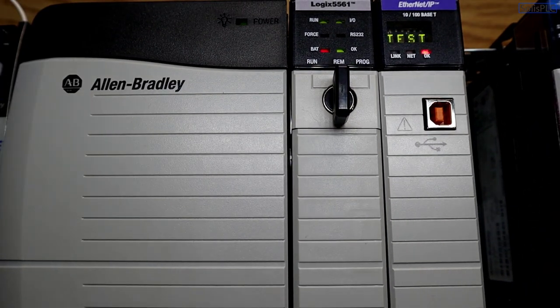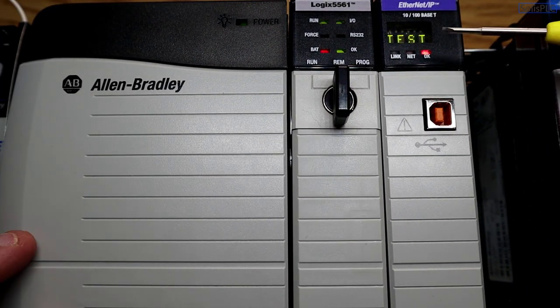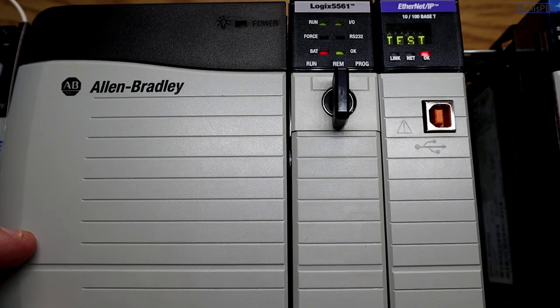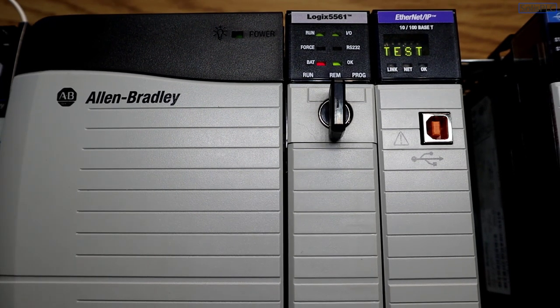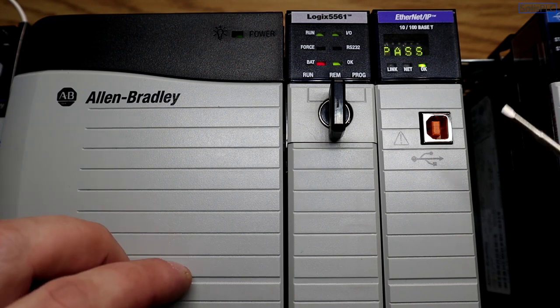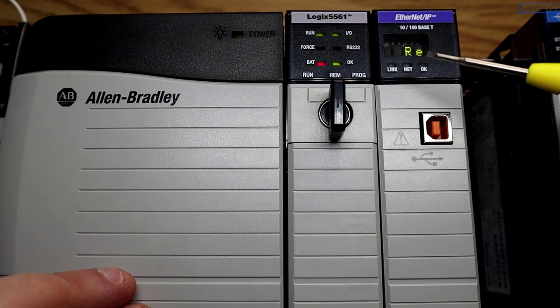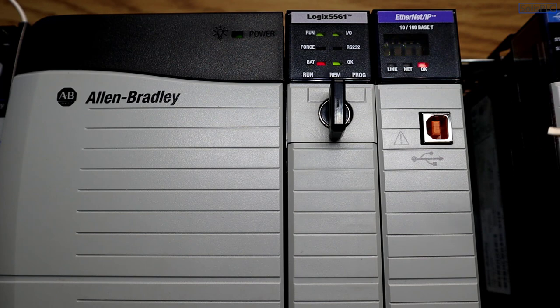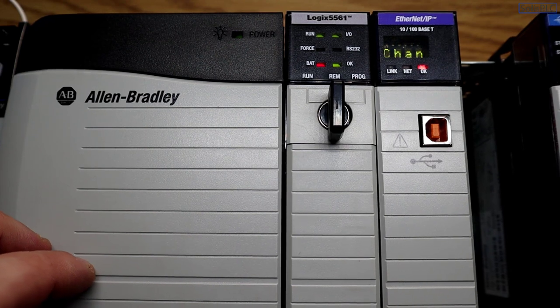So I'm going to put it back in, and do notice that I'm doing this while power is on. These modules are actually rated to be manipulated like such, but in a factory setting, maybe you have other devices in your panel, so I wouldn't necessarily recommend touching a live panel and making these modifications live. I do recommend that you power down and make sure that you're locked out and tagged out.